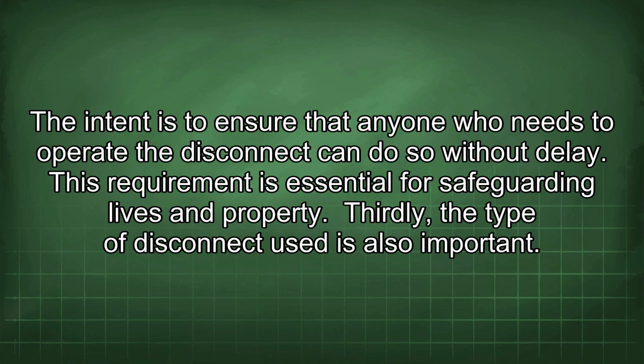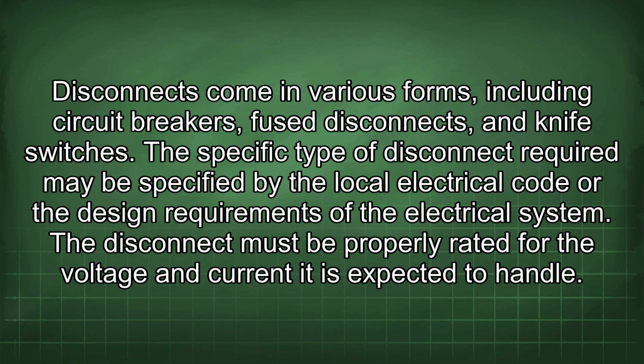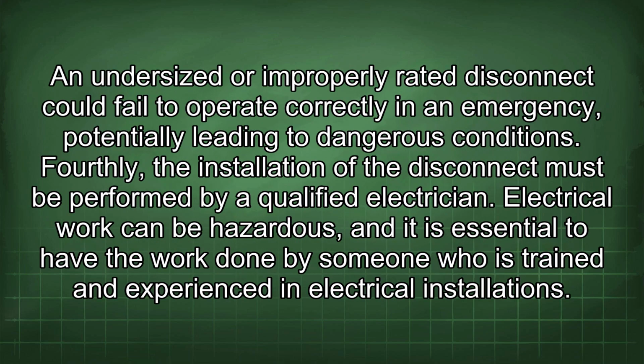Thirdly, the type of disconnect used is also important. Disconnects come in various forms, including circuit breakers, fuse disconnects, and knife switches. The specific type of disconnect required may be specified by the local electrical code or the design requirements of the electrical system. The disconnect must be properly rated for the voltage and current it is expected to handle. An undersized or improperly rated disconnect could fail to operate correctly in an emergency, potentially leading to dangerous conditions.